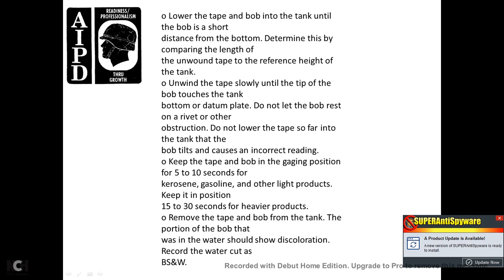50. Lower the tape and bob into the tank until the bob is short of the bottom — determine this by comparing the length of unwound tape to the reference height of the tank. Unwind the tape slowly until the tip of the bob touches the tank bottom or datum plate. Do not let the bob rest on a rivet or other obstruction. Do not lower the tape so far that the bob tilts, causing an incorrect reading. Keep the tape and bob in position for 5 to 10 seconds for kerosene, gasoline, or other light products; 15 to 30 seconds for heavier products. Remove the tape and bob from the tank — the portion of the bob that was in the water should show discoloration. Record the water cut as the bottom sediment and water.